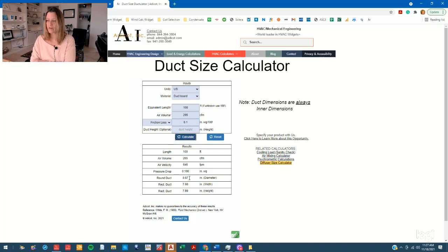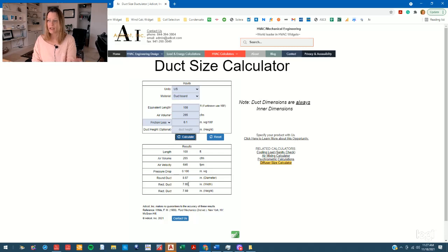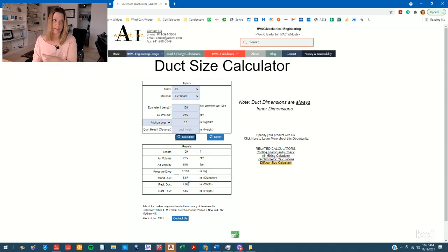You can calculate, and we can see that this gives you a round duct diameter of 9 inches, or an 8 by 8 rectangular duct.